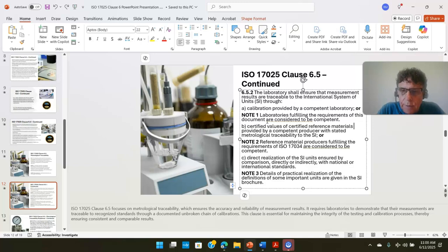They are ISO 17025 accredited. There are reporting requirements under section 7.8, which I will get to in a future video, but there are requirements that ISO 17025 calibration companies need to put on their calibration reports, and they need to have the expanded uncertainty of measurement I mentioned, and they need to be in accordance with ISO 17025.